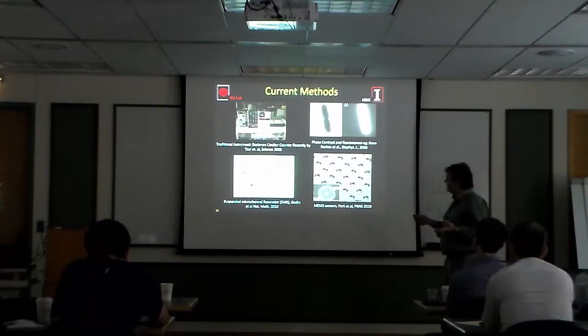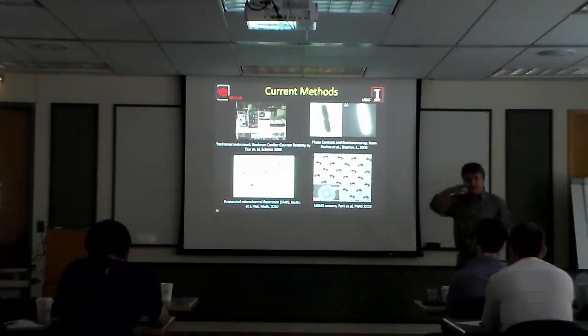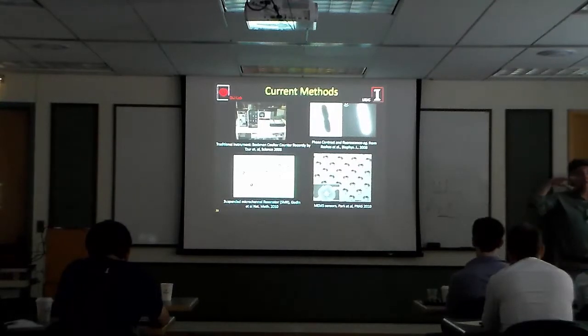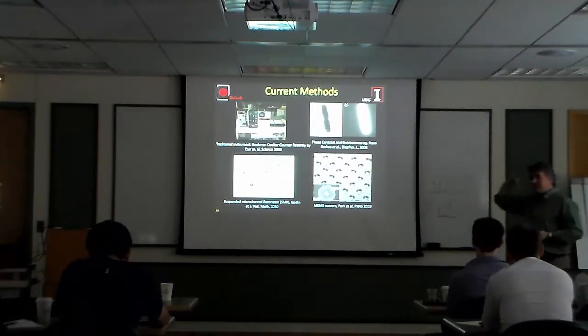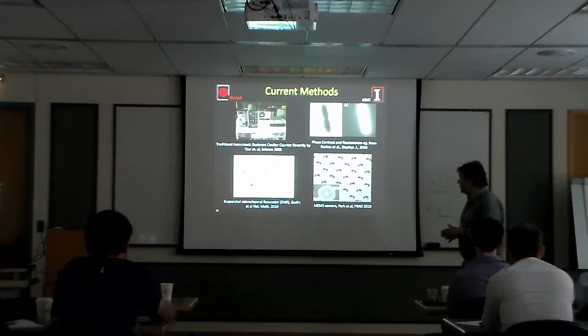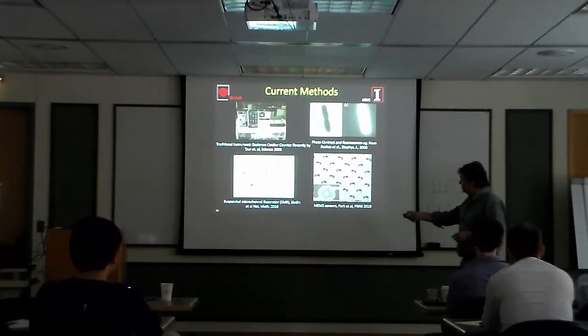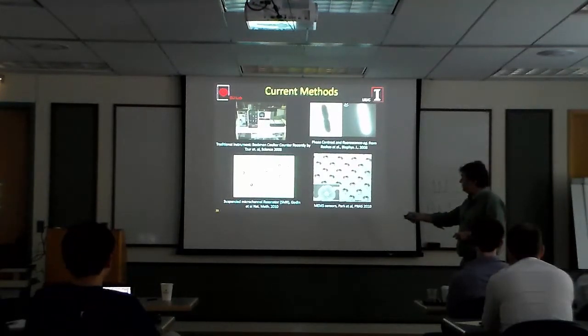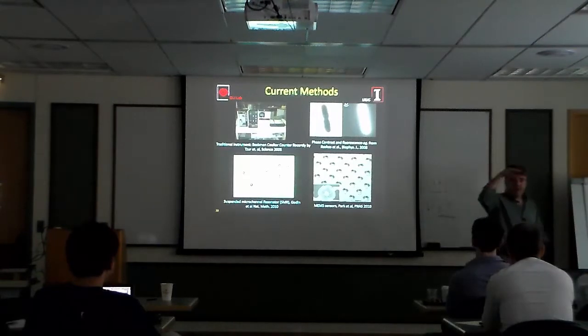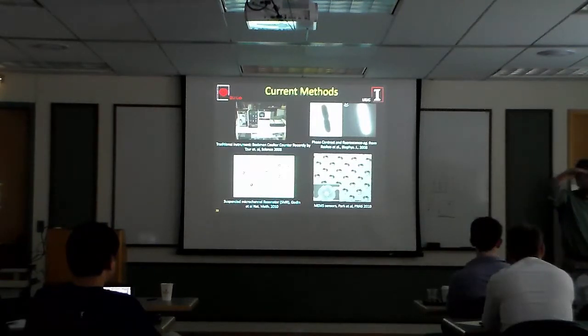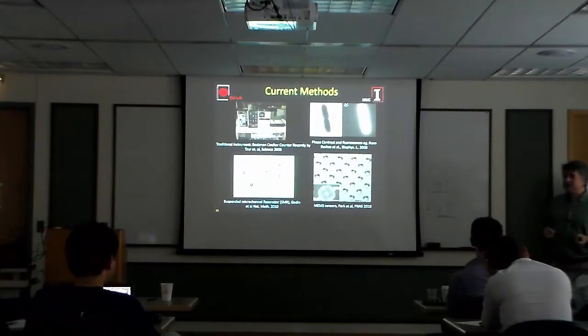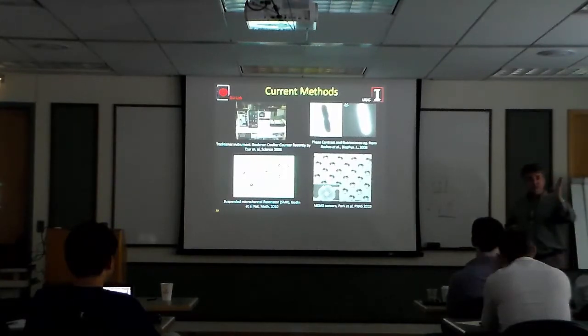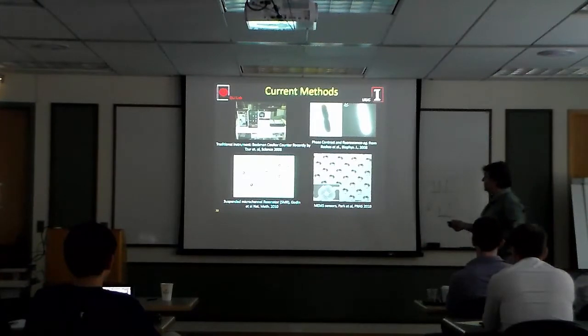And they had a very nice idea of having a vibrating cantilever, pretty much like in AFM. So you have a resonant frequency of this cantilever, but now you have a channel through it. And when you flow the cells through, the mass of the cantilever changes a little bit, and therefore the resonant frequency changes. So if you measure the shift in frequency accurately, you're able to back out the mass. So I think it's very interesting technology.